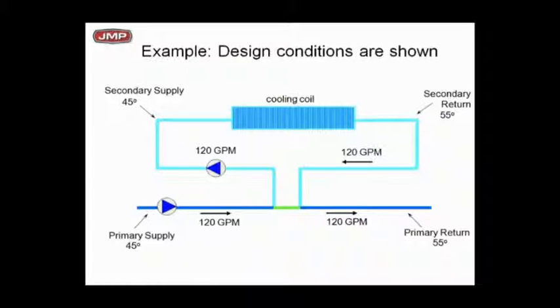Let's add some temperatures to our cooling coils and see what the impact is of changing flow rates in the primary and the secondary to the actual temperatures we see. Remember, most cooling coils are going to be picked probably on a 45 degree supply - or you could pick them on 42 or 40, whatever you want. But on average, it's going to be around 45 because of dehumidification. If you try to dehumidify the air, you've got to get the water cold enough to start getting moisture out of the air.